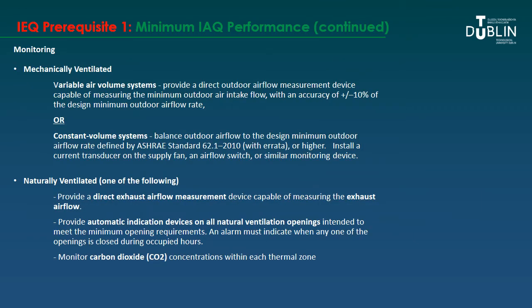The second part of the prerequisite covers monitoring, which is related to the construction phase. For mechanically ventilated variable air volume systems, you need a direct outdoor airflow measurement device measuring particular flows with specified accuracies. For constant volume systems, you balance the outdoor airflow to the design minimum per ASHRAE or install a current transducer on the supply fan. For naturally ventilated buildings, you provide a direct exhaust airflow measurement device, an automatic indication device on openings, or CO2 monitoring.